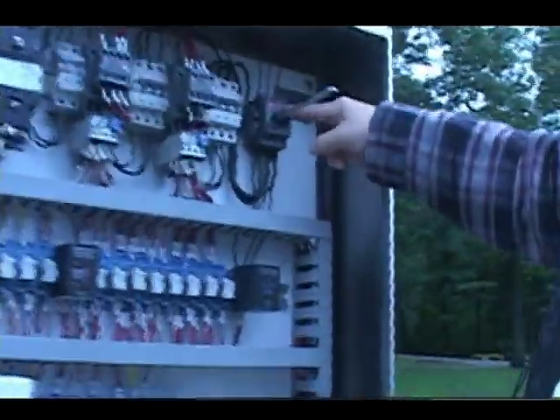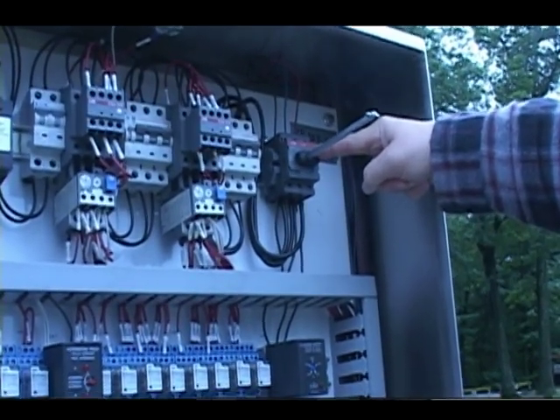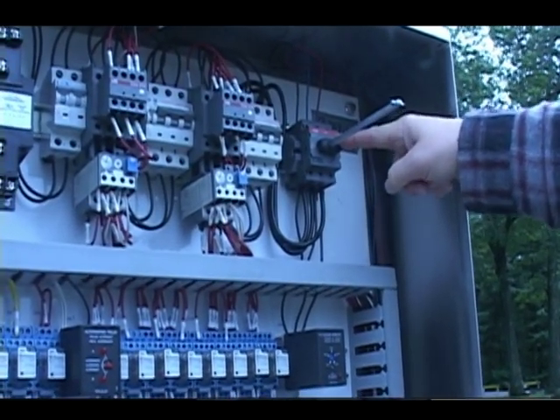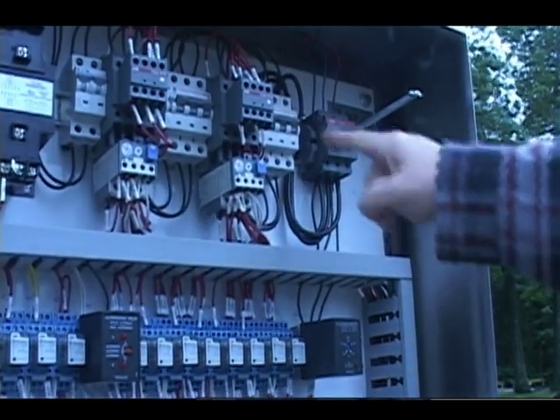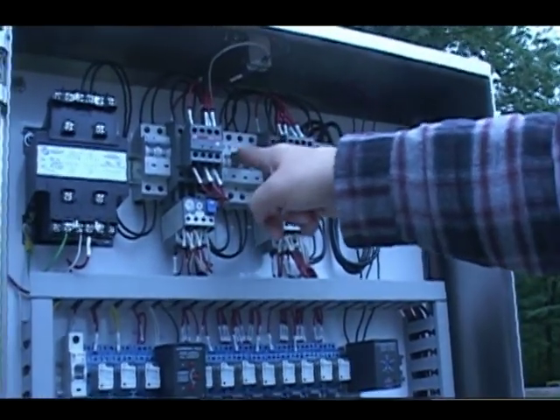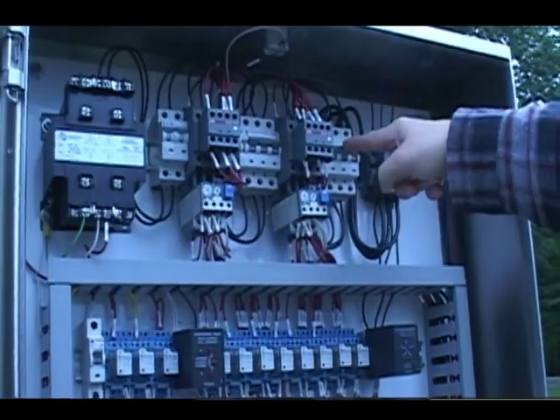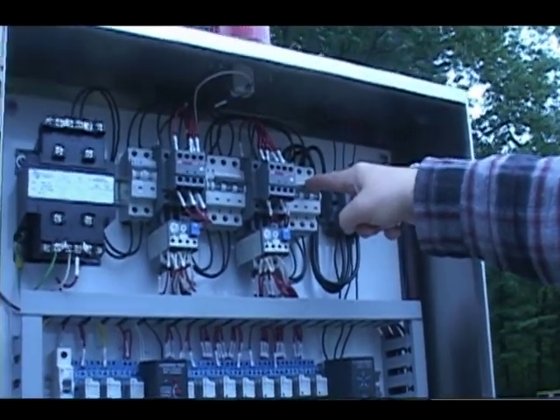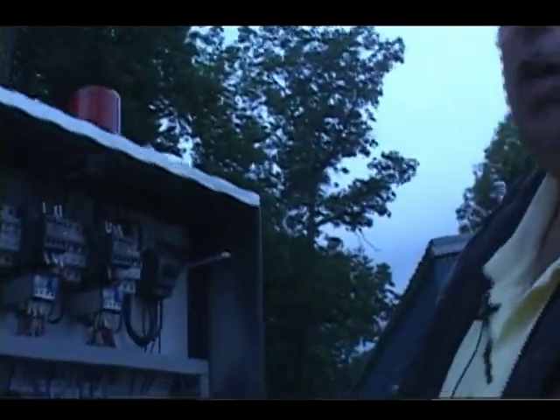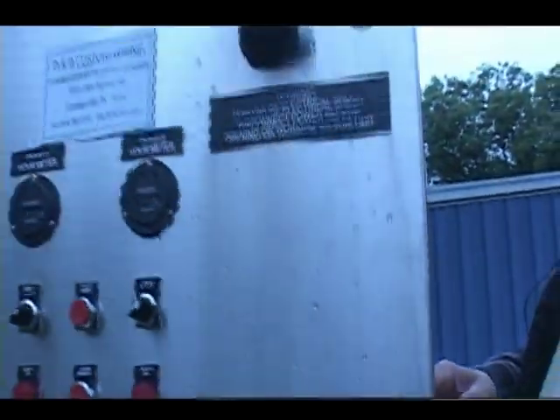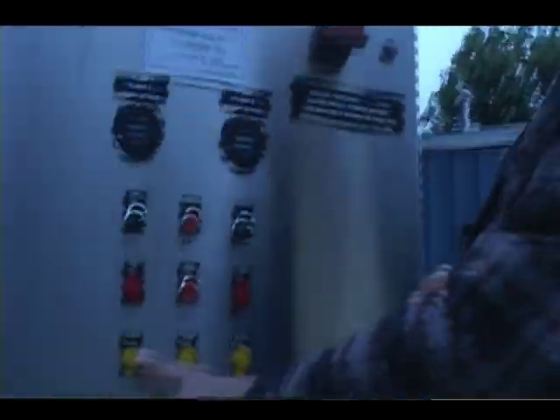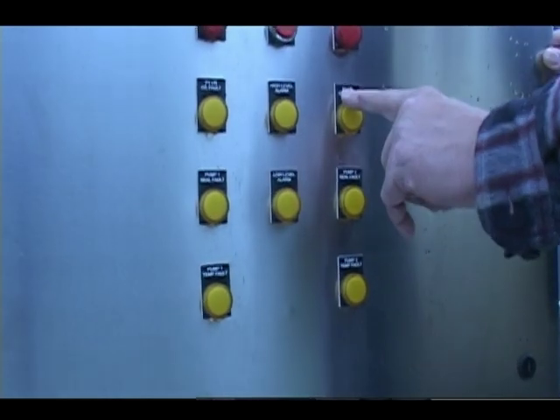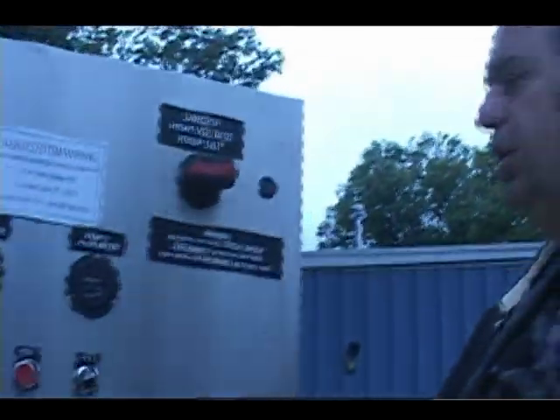Let's talk about components. This is the main disconnect. It's a non-fused that turns power off to the panel. Each of the pumps has their own circuit breakers here or here. It also has an auxiliary that says that the pump is tripped for some reason, and if it did trip, the same with an overload on the starter, then what happens is, again, it's this pilot light that wants to turn on. So it's one of those two things that's showing you the alarms.